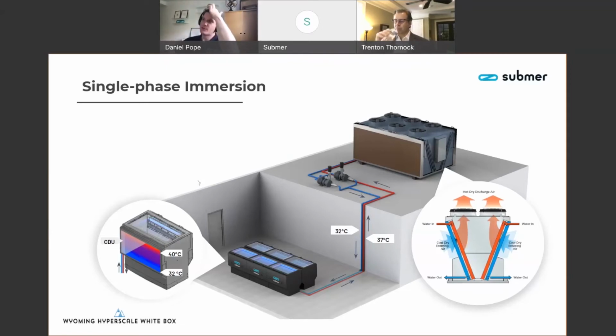From what I've heard, your team is really looking at optimizing the secondary cooling loop from a design perspective, and also from an AI and orchestration perspective as to when and how those loops are leveraged. What's super interesting is the dielectric fluid we use doesn't freeze, it can support down to -40 Fahrenheit without freezing. We're also starting to see the first implementations of immersion fluid being taken directly out to the dry cooling infrastructure.